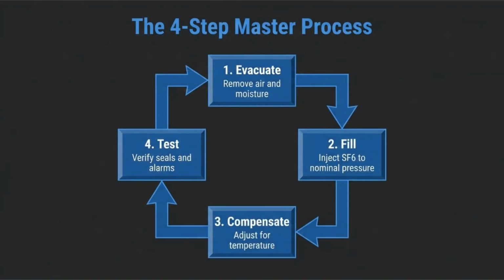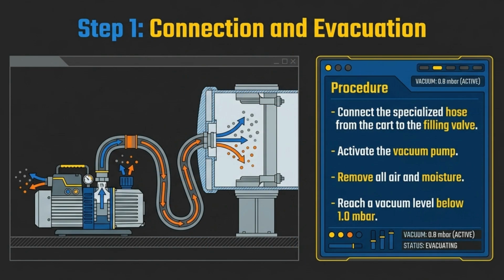The four-step master process is simple yet critical. Evacuate air and moisture, fill SF6, compensate for temperature, and test seals and alarms for total reliability. Step 1 is connection and evacuation. Connect the specialized hose, activate the vacuum pump, and remove all air and moisture. Ensure a vacuum level below 1.0 millibars.